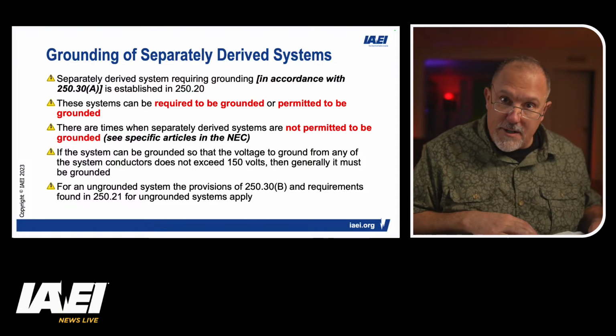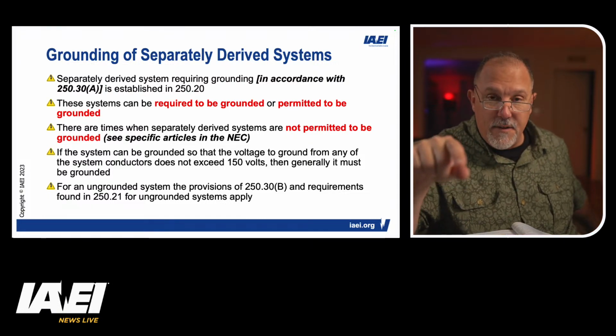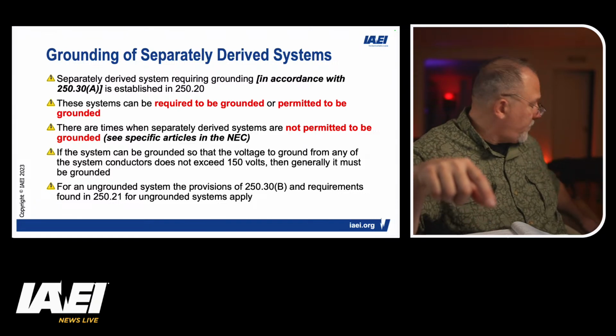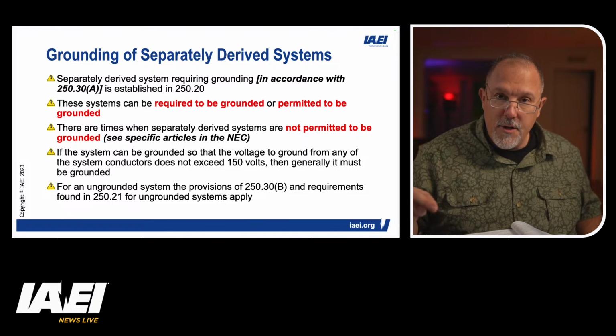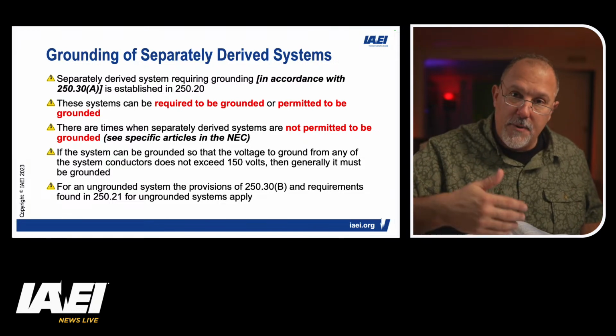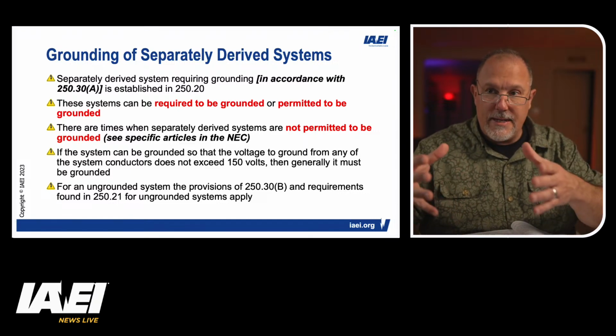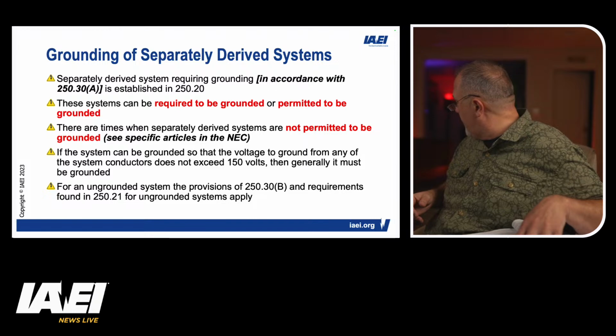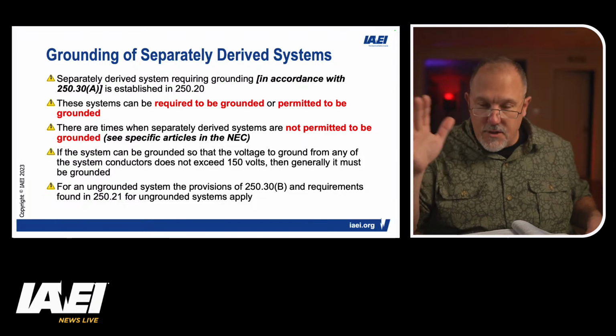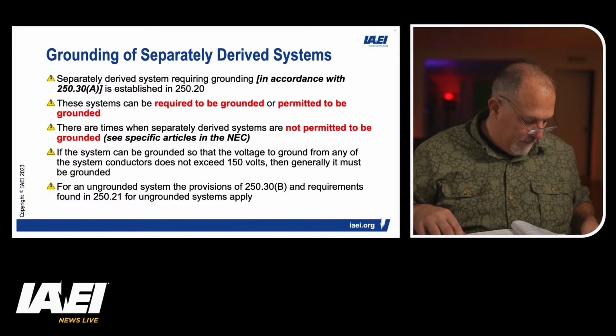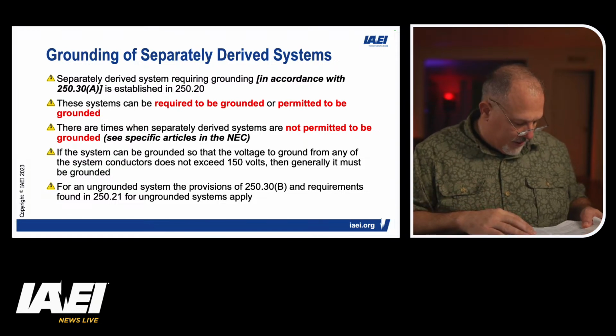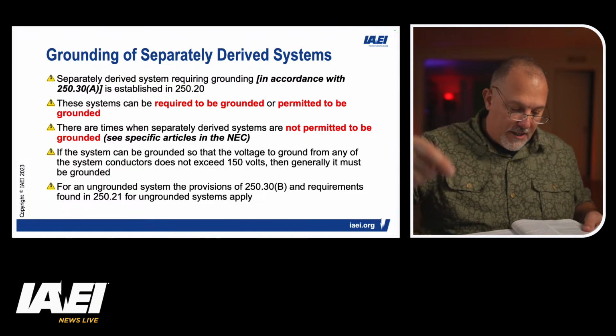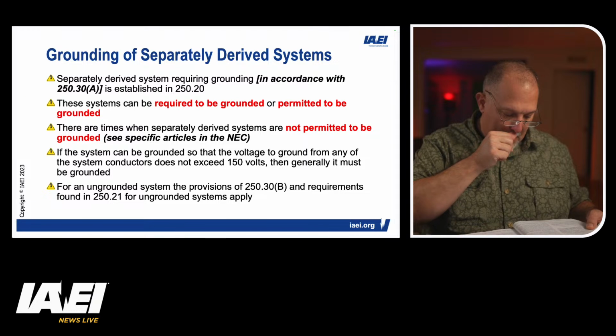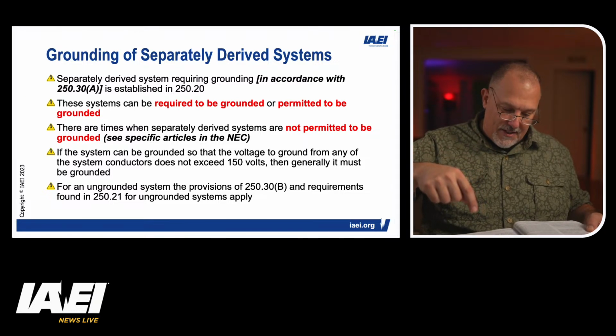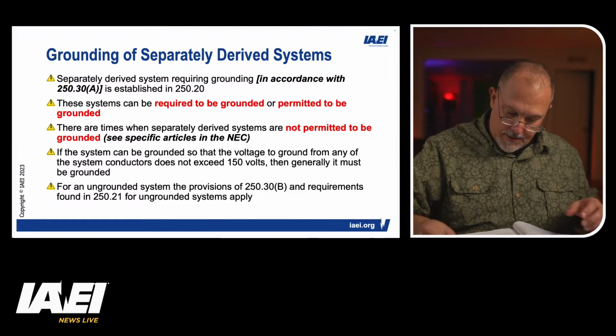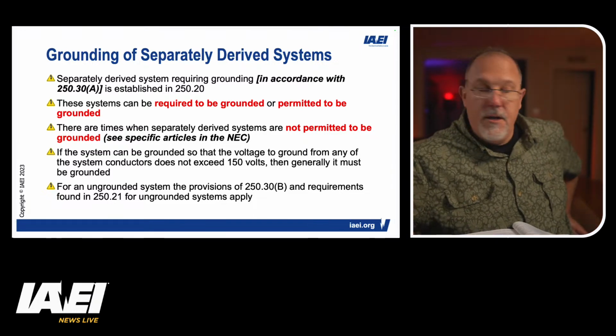A2 is your supply side bonding jumper. These should sound very familiar on your services side because we have supply side bonding jumpers. We do our bonding and grounding at the separately derived systems very similar to your service applications. Supply side bonding jumpers, grounded conductor, grounding electrodes, grounding electrode conductor, single separately derived system, grounding electrode conductor, multiple separately derived systems, and then you've got your ungrounded systems. Okay, so those are the areas.